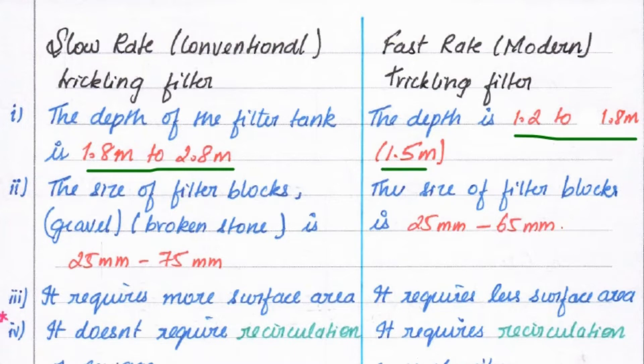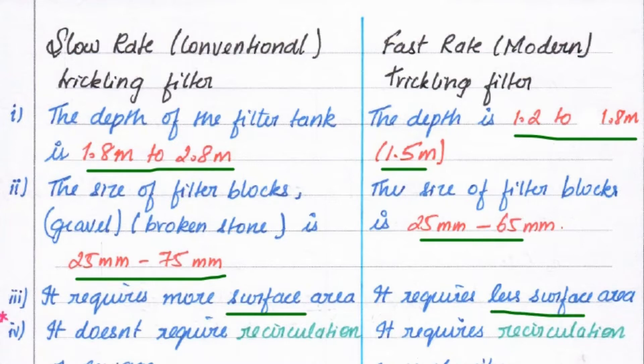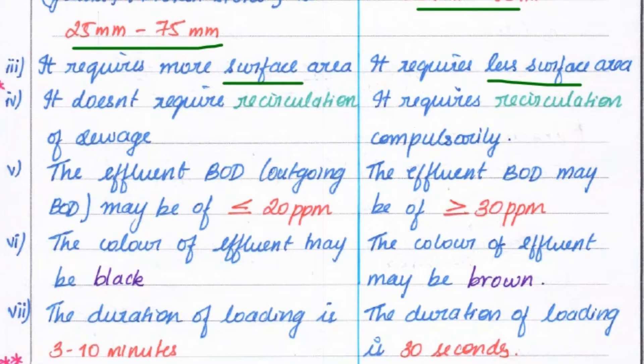The size of filter blocks in the slow rate trickling filter is 25 mm to 75 mm, but in the fast rate it is 25 mm to 65 mm. The slow rate trickling filter requires more surface area, while the fast rate trickling filter requires very less surface area.